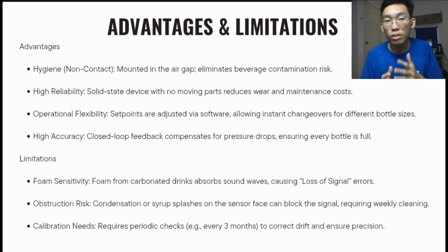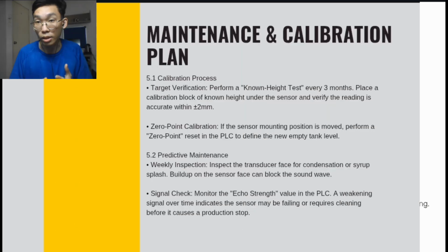To mitigate these risks, we propose a simple maintenance strategy. For calibration, we will perform a known-height test every 3 months to verify accuracy within plus or minus 2 millimeters. For maintenance, we require a weekly inspection to clean the sensor face. We will also monitor the echo strength in the PLC to detect weak signals before the line stops.